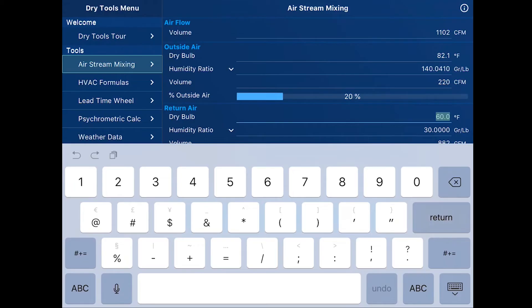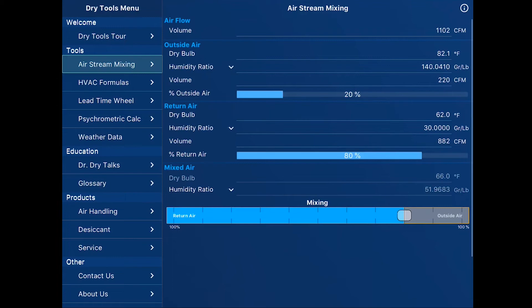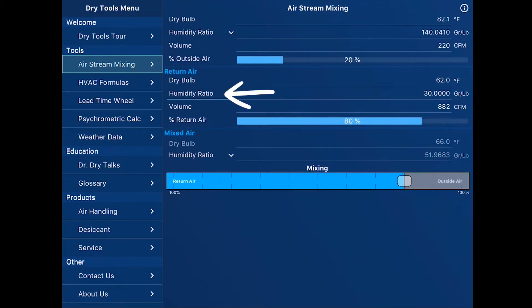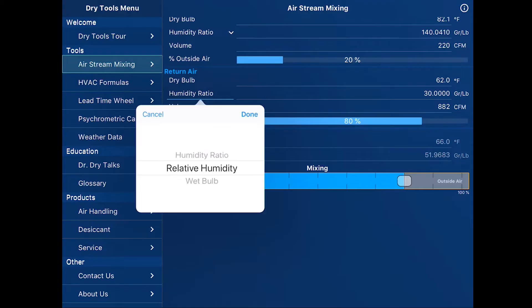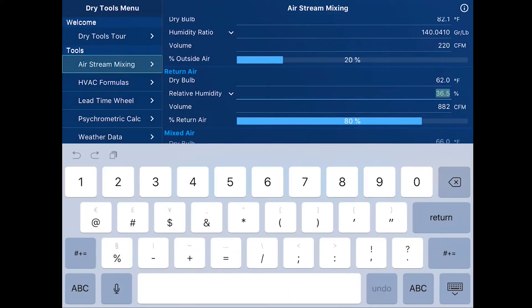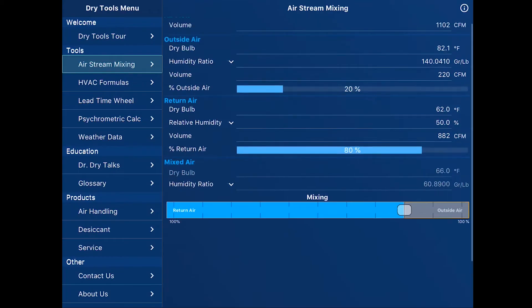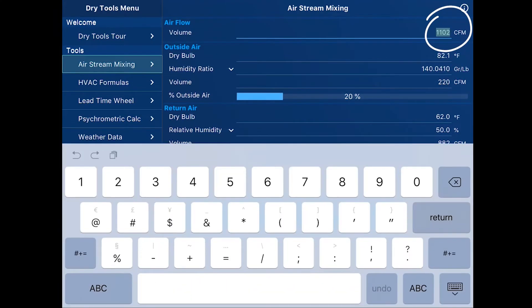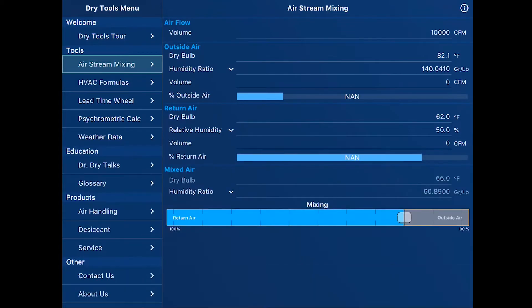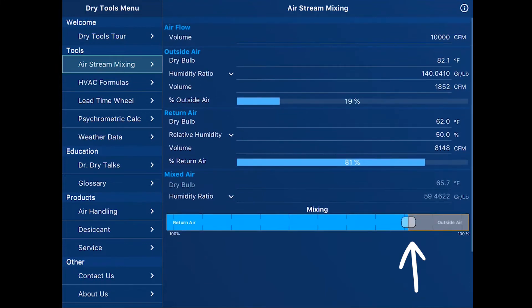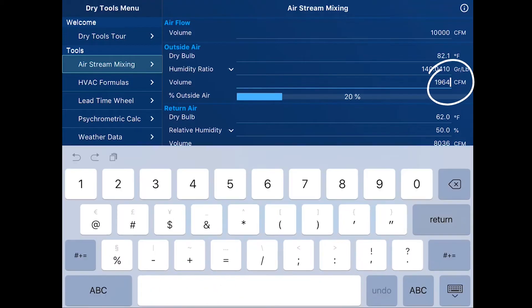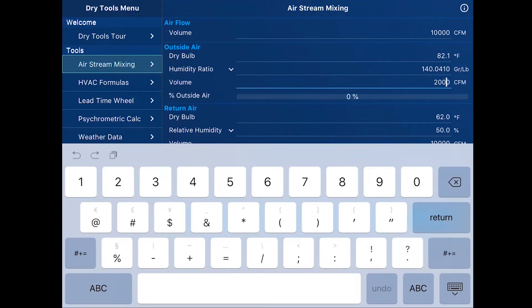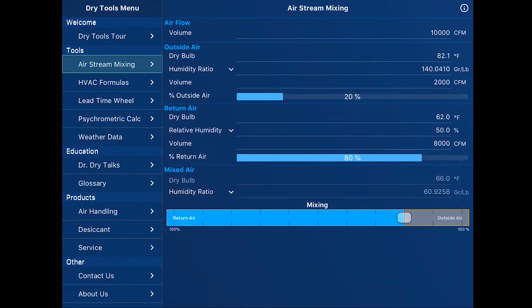It's defaulted, but let's pick an application of a hospital surgical suite, which we would normally see at 62 degrees Fahrenheit. And normally it's going to be expressed to us not in humidity ratio, but in relative humidity. So I can change that to relative humidity and now enter 50% relative humidity. The amount of air of the two air streams can be changed by starting by adding our total CFM. In our example today, if we had four operating suites, that would be 10,000 CFM. At the bottom of the page, I can slide my mixing bar and get to 20%, or I can just change this to say 2,000 CFM, which would be 20%.